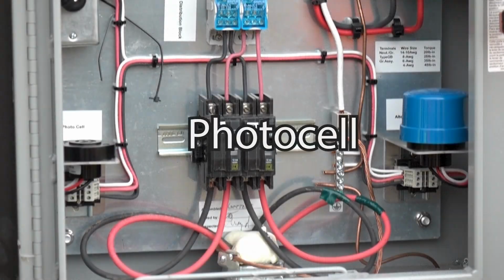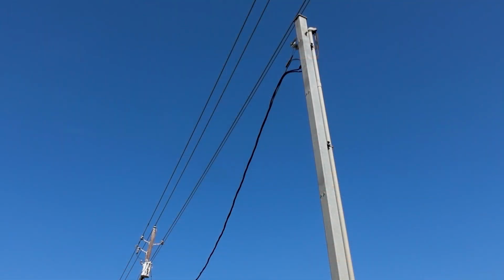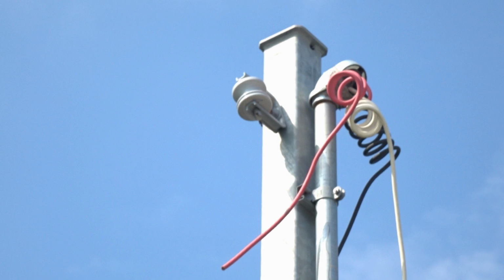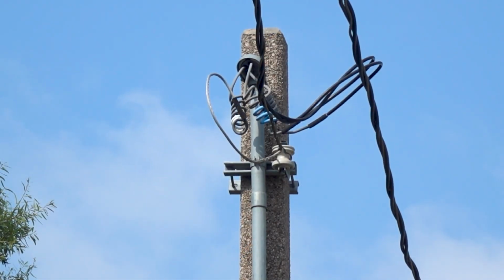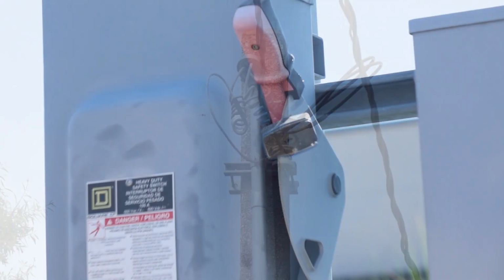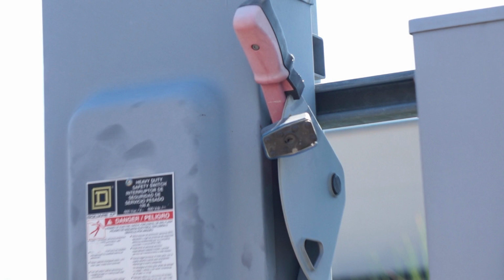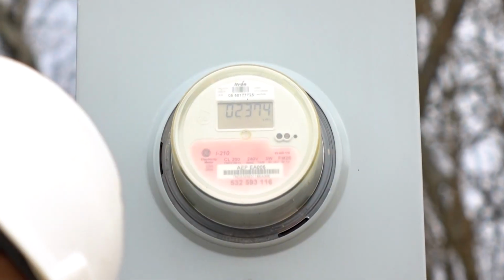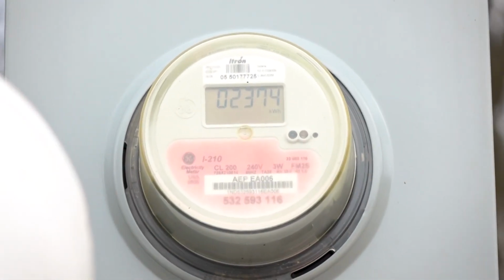The photocell is mounted inside the Type A custom enclosure and placed accordingly. The service drop conductor vertical clearance height from grade at the lowest point is as required by the NEC. Conductors are identified with the correct colors at the weatherhead. Conduit support spacing and materials meet specifications and standard sheets. The safety switch, when required, meets specifications. The utility meter, when required, is properly secured.